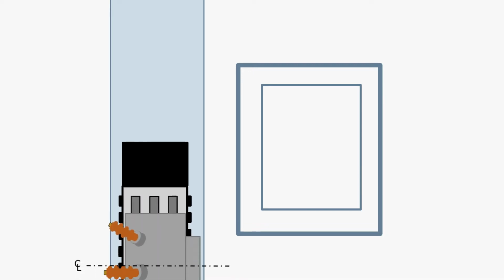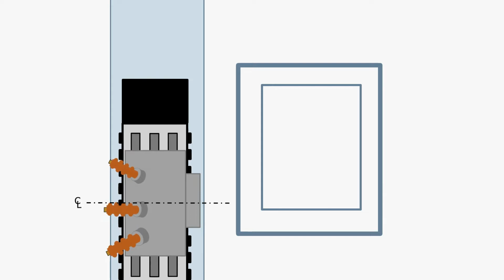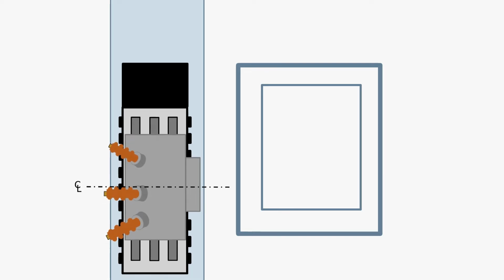The second option we have for installing a transformer is to jack it from the trailer onto the transformer foundation. Let's see how that's done. Here we have a typical transformer foundation with a surrounding bund. Firstly, we drive the trailer up to the transformer bund, getting as close as possible. As a substation designer, we therefore need to position the road as close to the transformer bund as possible.